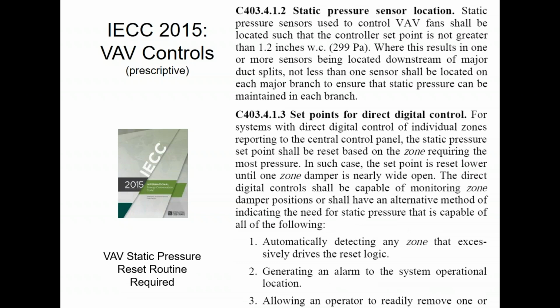You also have to do static pressure reset. This is not new. This was required in the previous version as well. That means that I have to look at all of my DDC controlled VAV boxes, and if nobody's 100% open, obviously I'm giving them too much airflow, so I need to start reducing the static pressure down. Right? So instead of giving them 1.2, I'll give them 1.1 and see what happens. I'll give them 1.0 and see what happens. And then when somebody finally opens up near 100%, then I would start raising the static pressure back up again. That's fairly easy to do with DDC controls.